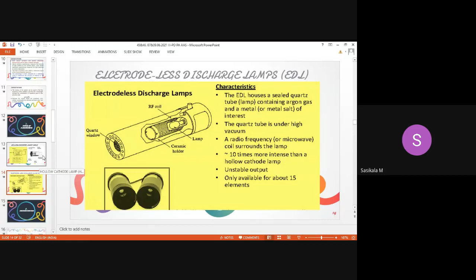The radio frequency coil surrounds the lamp, and it is approximately 10 times more intense than a hollow cathode lamp. So it will be of higher intensity than the hollow cathode lamp, but an unstable output of radiation occurs. Then it is available for only about 15 elements, not for all the elements. But it is more intense than the hollow cathode lamp. However, we will not be using the electrodeless discharge lamp widely in instruments. You could find HCL lamps widely in the instrument, but there are two types of lamps used as the source of light in atomic absorption spectroscopy. One is HCL, another one is EDL. HCL is hollow cathode lamp, EDL is electrodeless discharge lamp.